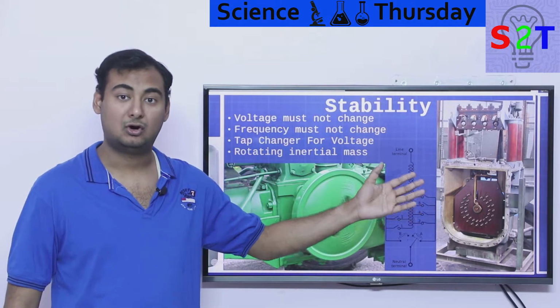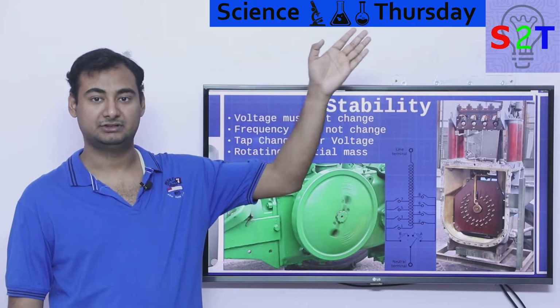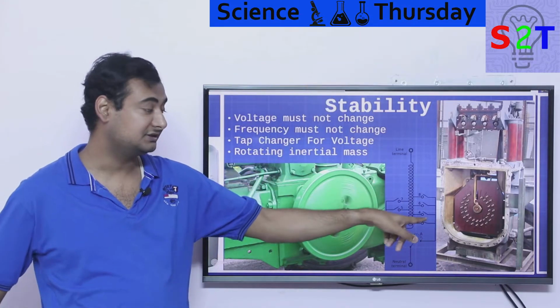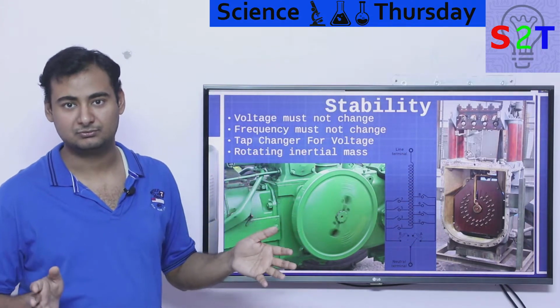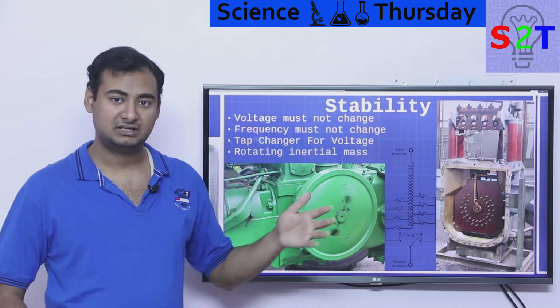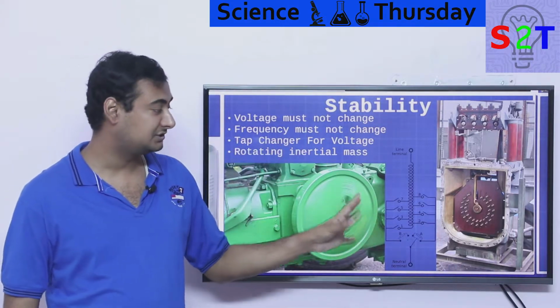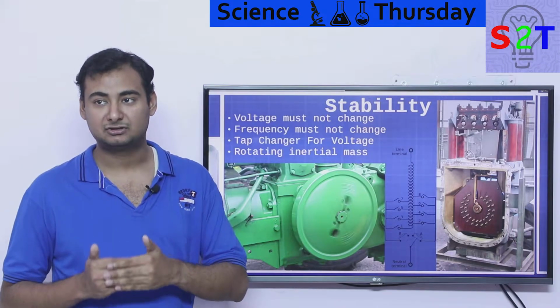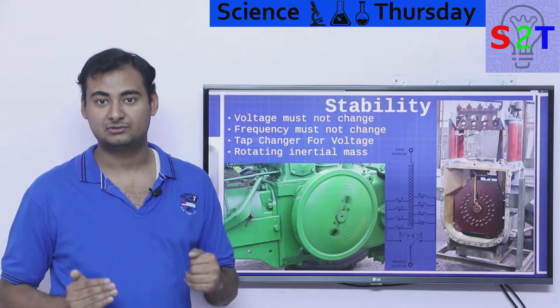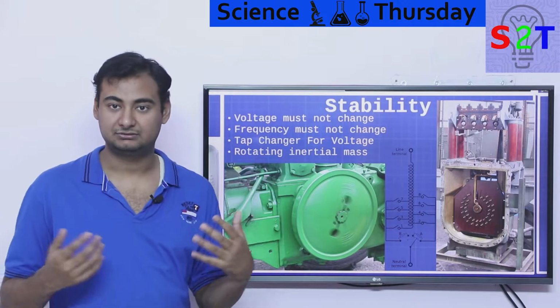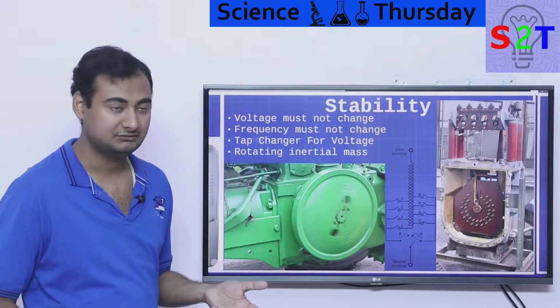Basically, it's what we call an on-load tap changer. You can check my video about large transformers, because this is where they are. They're generally not on your home substation nearby, but on big substations. They make sure the voltage always stays within tolerance, keeping fluctuation below 10%, so your building doesn't catch fire because of electrical faults.